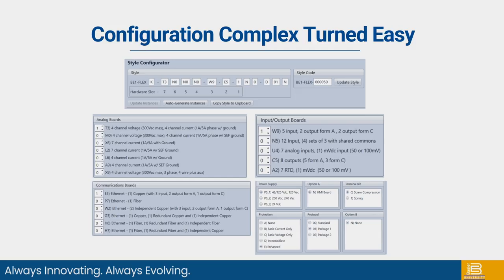So with this tool, you select up to 4 analog boards. You select 1 communication board. You select the necessary input-output boards, and then go through the other options at the bottom right, such as the 3 power supply options, the terminal kit, the protection packages that are available from none, current only, voltage only, intermediate to enhanced, and the protocol packages, which have Modbus, DNP3, and also IEC 61850 with GOOSE messaging, MMS, and file transfer.